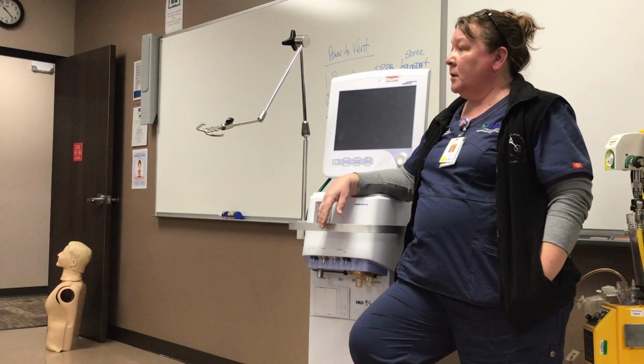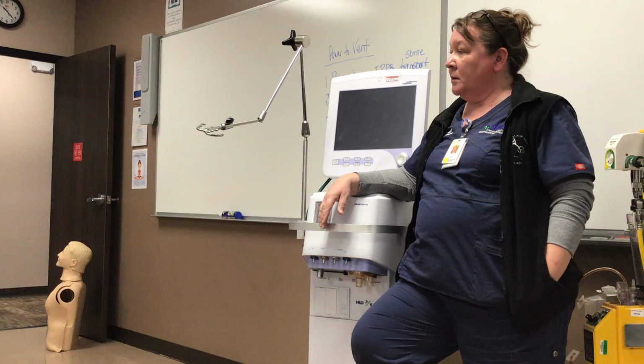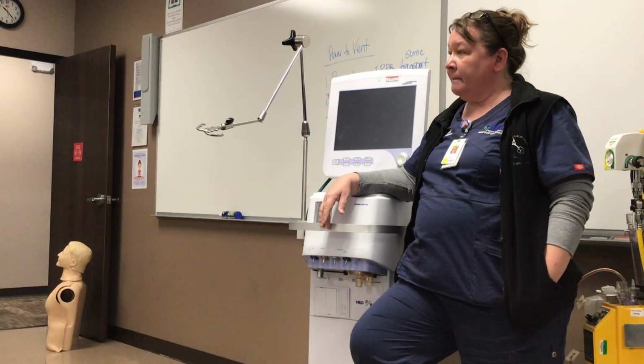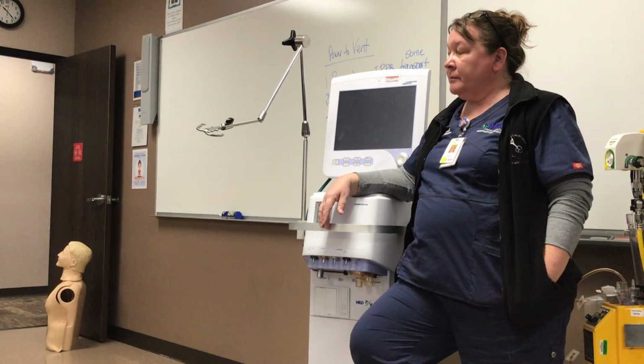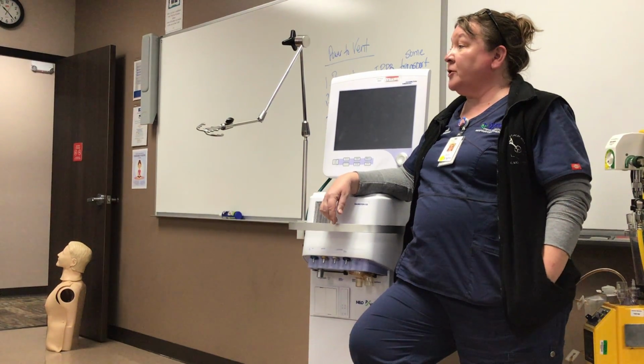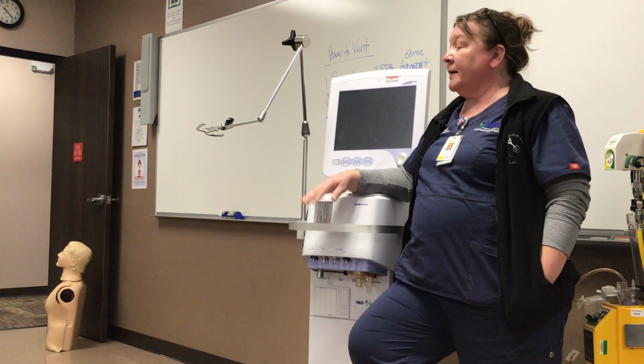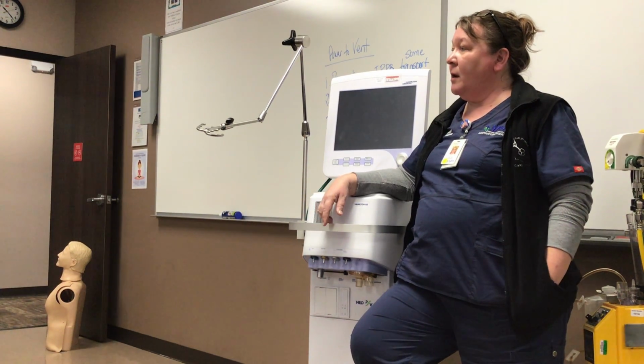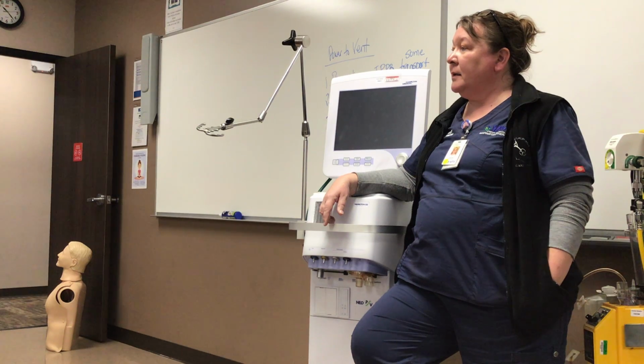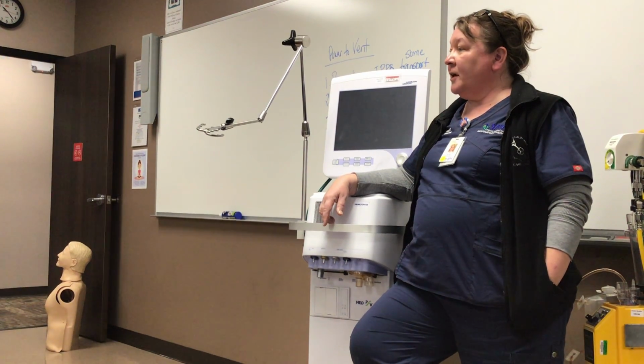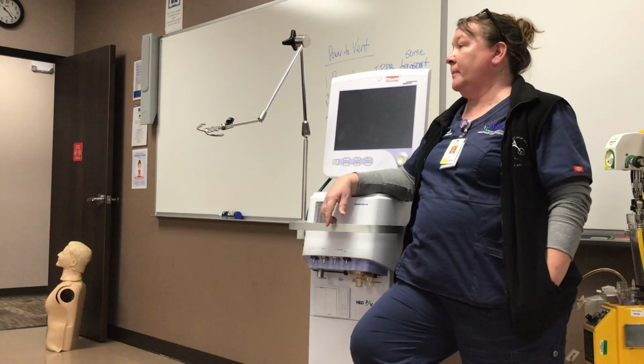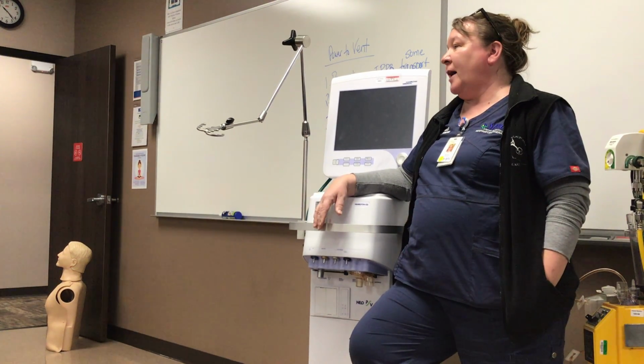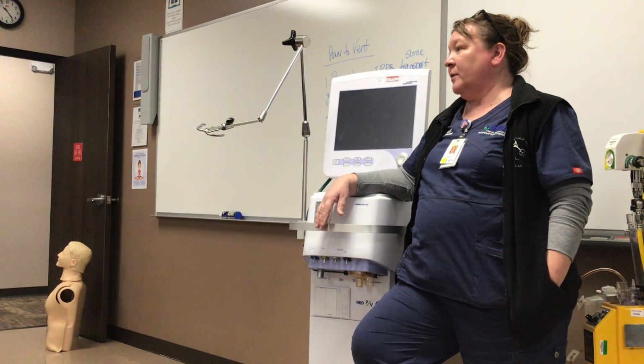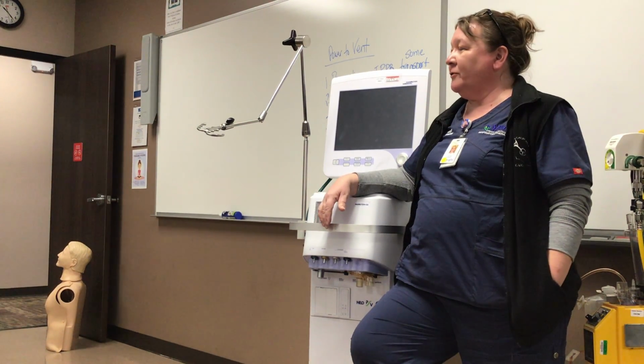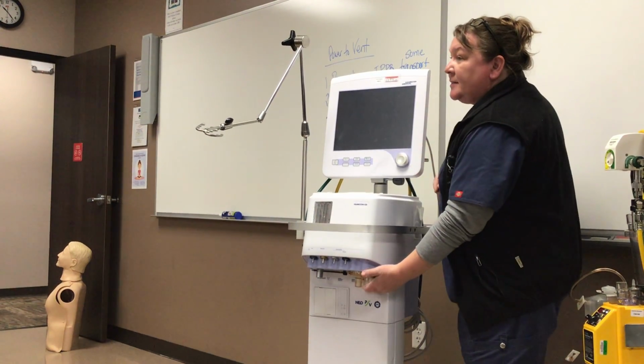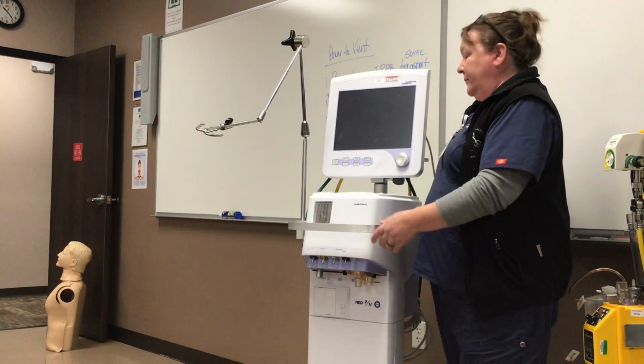And for switching out the valves there, or the little magnets, are they generally all the same color, or do you have different colored ones? They're the same per manufacturer and per ventilator. So every vent, like this G5, every one will look like that. Okay, so essentially we might have a different G5 at Mercy. Is it a different color? Well, yeah, they were blue. They were the exact same thing. So maybe it's just a newer valve. This is an old valve that's been in here forever because we haven't had to replace it. But that's single patient use. I don't know for sure if they go through sterile processing or not. This part does, but I don't know if they take it out and wash the whole thing out. Yeah, and replace it with a new valve.